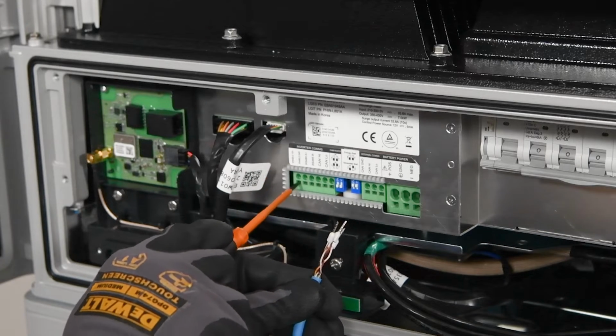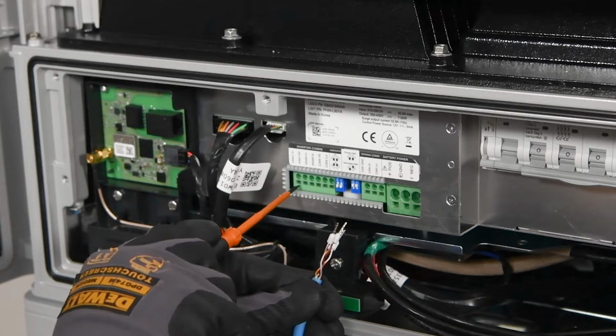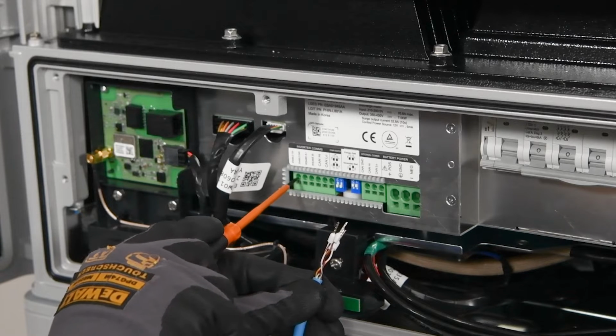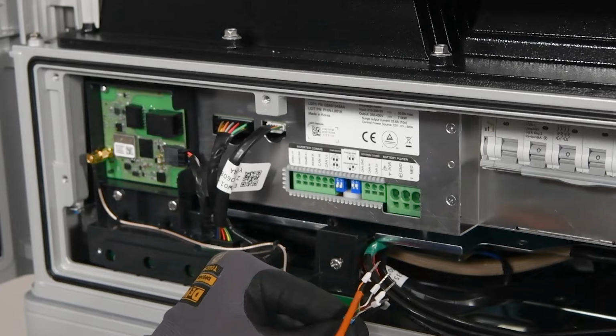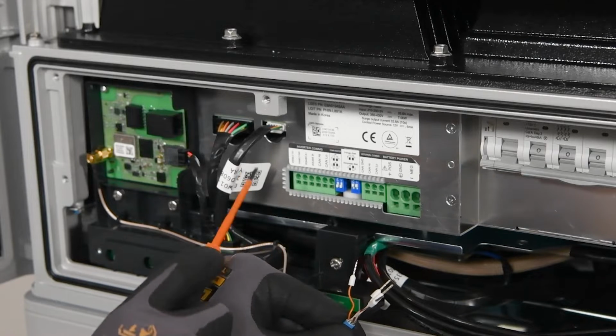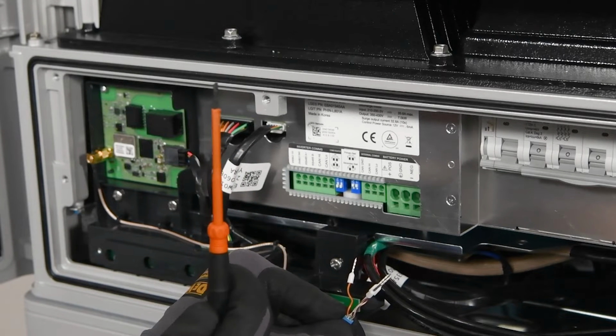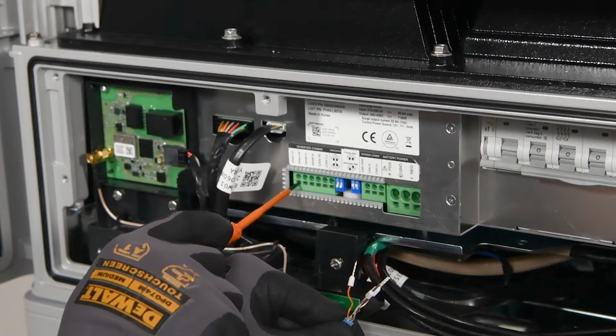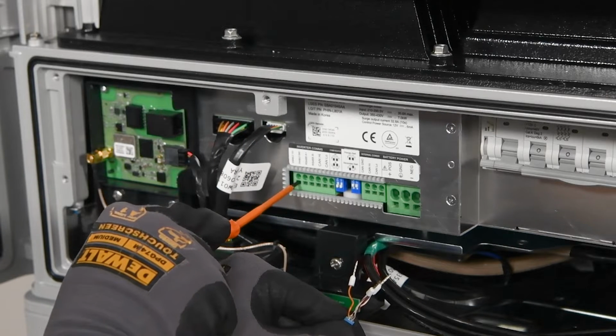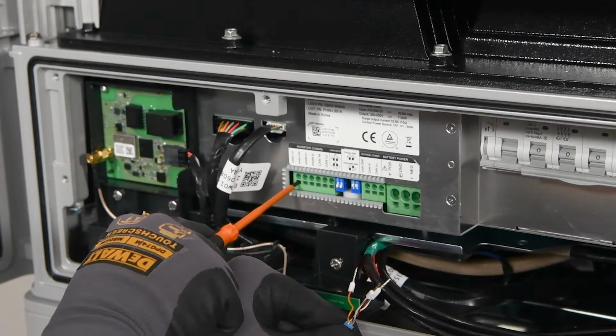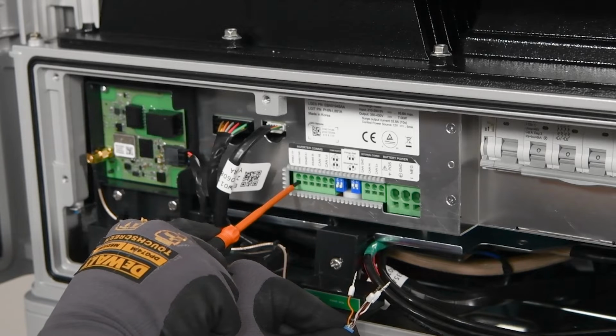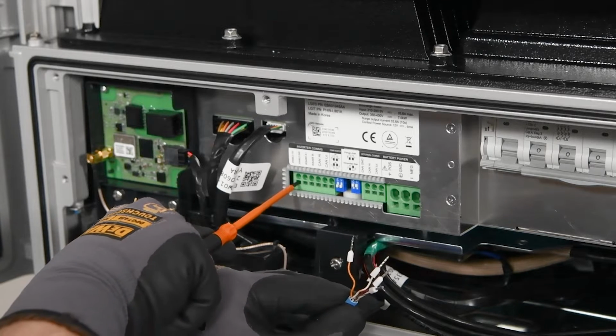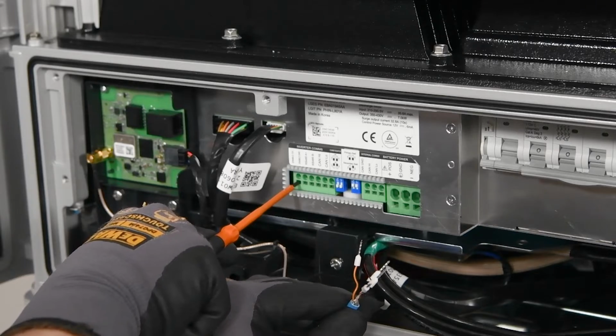When you go to connect these communication cables or our ferruled ends into the terminal housing or the inverter comms ports, you'll notice that there are 2 holes, one on top and one on bottom. The circular hole is where the cable or the ferrule will go, and we can take a very small flat end screwdriver, insert it into the bottom square hole, and what that's going to do is open up the jaws at the back of the inverter comms port to allow us to insert the communication cable easily.